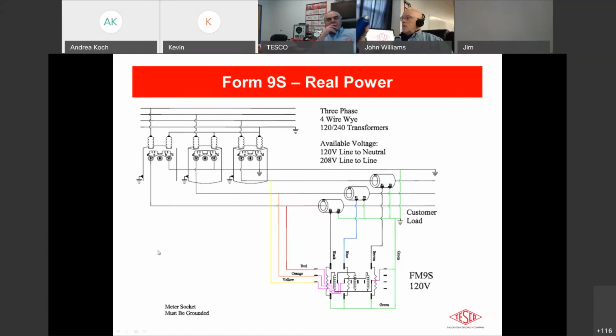Yes, sir. So everybody down here is going to the 9S meter because they can get different voltages from the Y bank for 120/208, 120/240, 277, 480. They can get whatever they want. It's much safer, cleaner, easier to work with, especially if you're troubleshooting. So everybody's going to the 9S meter down here and getting rid of everything else.